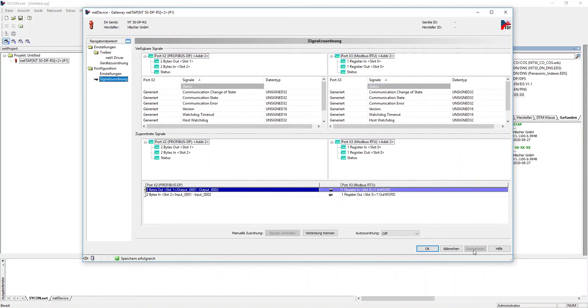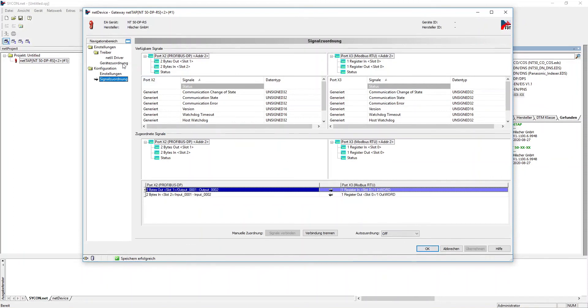Be cautious with the function automapping, because it will force the structure of one protocol onto the other and will override the configuration of the process data done beforehand. It's also irreversible.